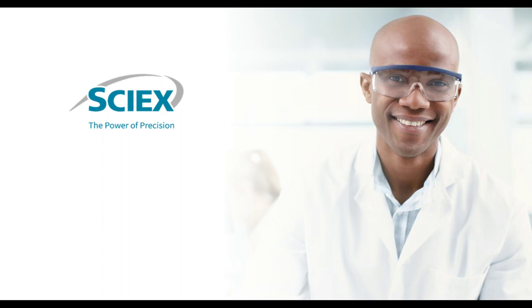Thank you, Peter. How many injections will a cartridge last? Okay, so because we're using a bare-fused silica capillary now, a lot of us might have had prior experience with a coated capillary, a neutral capillary, or an FC coated capillary, which generally we'll say lasts for about 100 runs or could certainly last longer, but that's generally what they are marketed as, at least 100 runs. With a bare-fused silica capillary, I think you could expect to be in the multiple hundreds of runs because there is no degradation of that coating.